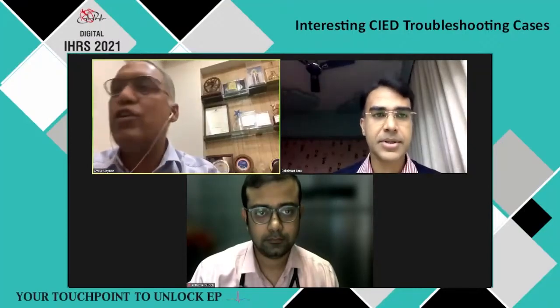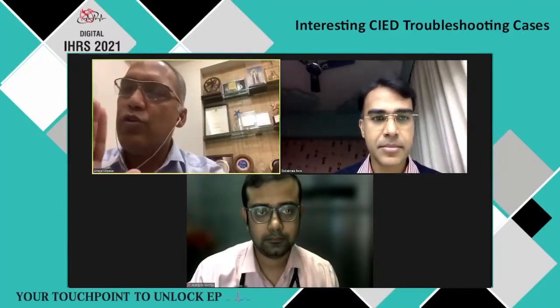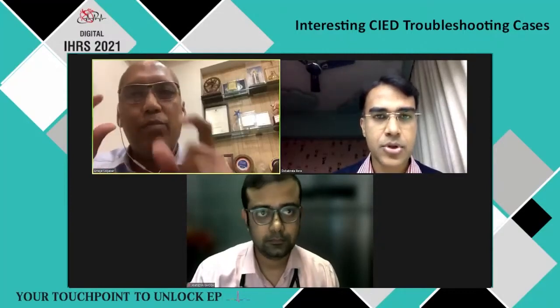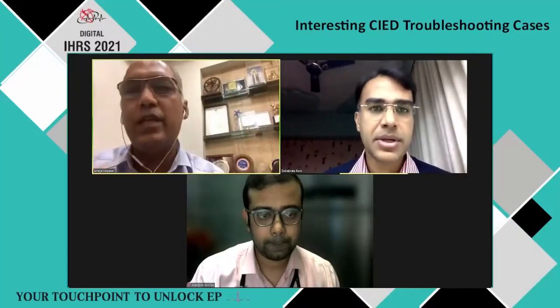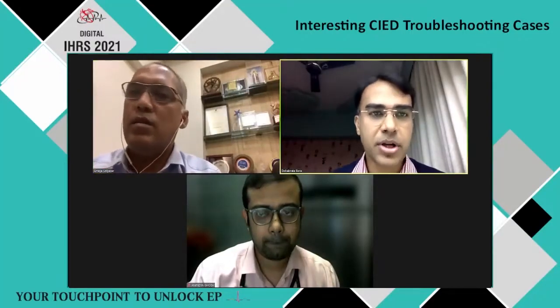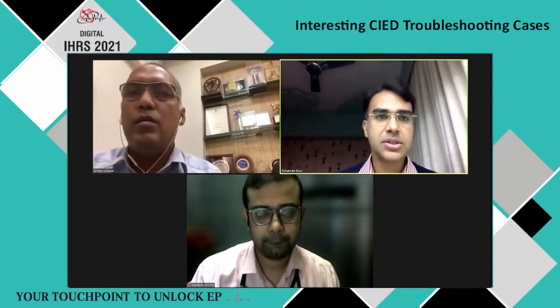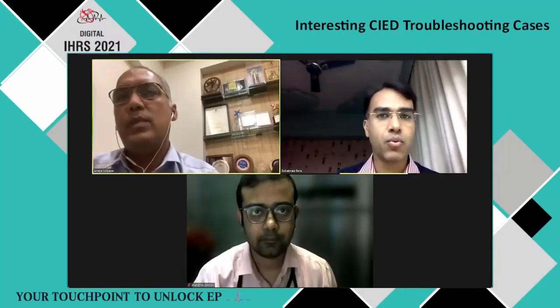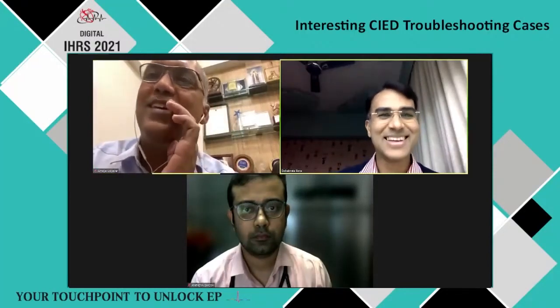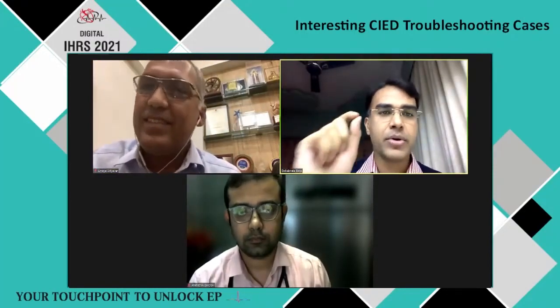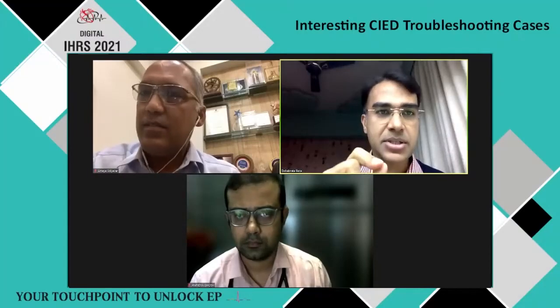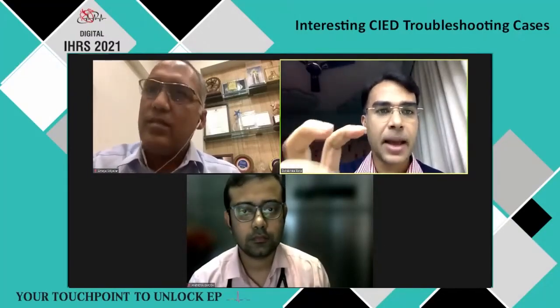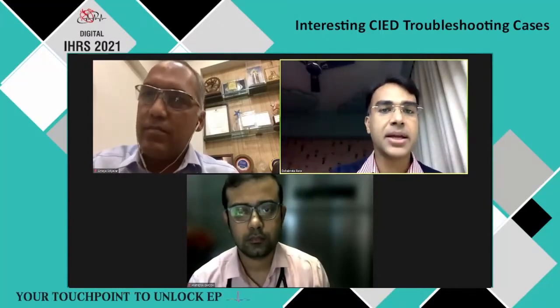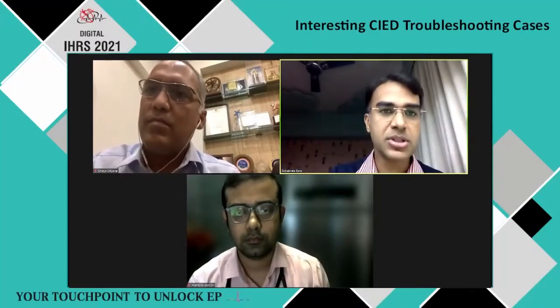And just one last question, for the sake of the fellows: just define what you mean by polarization signal and evoked potential? Because it's a very important concept. A lot of people don't understand what the polarization signal is when it comes to pacing. One, what is evoked response? The auto capture algorithm functions based on the ratio between these two. We had some good descriptions about anatomy from Dr. Cabrera. So evoked response is when the lead paces at the ventricle, or even the atrium nowadays. Let's talk about the ventricle. When the lead paces, it stimulates the heart and captures the local myocardium. That gives back an impulse which is recognized as an evoked response by that lead.